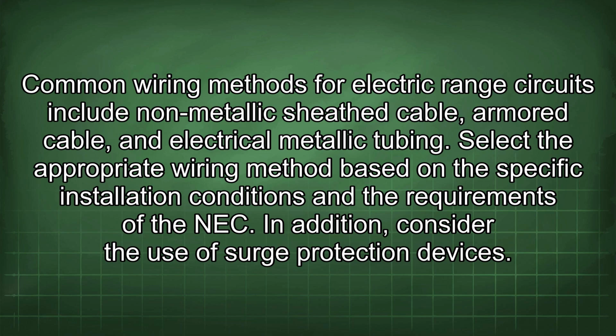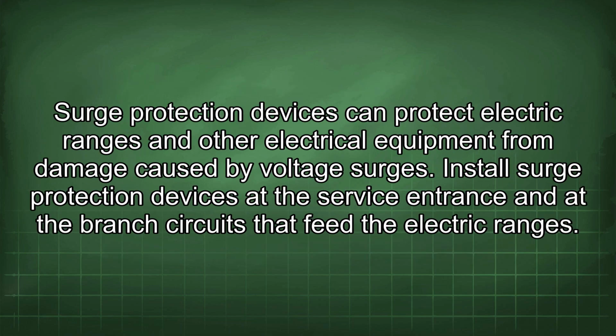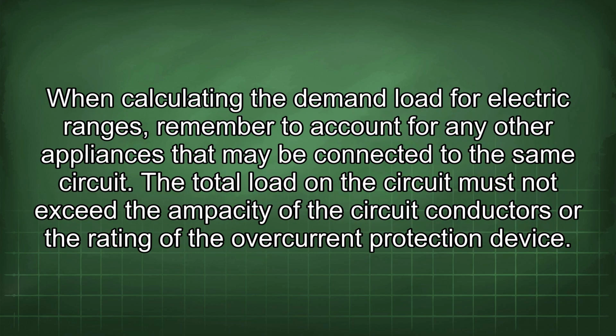In addition, consider the use of surge protection devices. Surge protection devices can protect electric ranges and other electrical equipment from damage caused by voltage surges. Install surge protection devices at the service entrance and at the branch circuits that feed the electric ranges. When calculating the demand load for electric ranges, remember to account for any other appliances that may be connected to the same circuit.